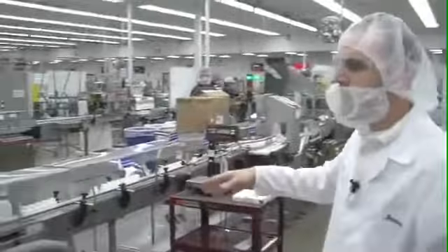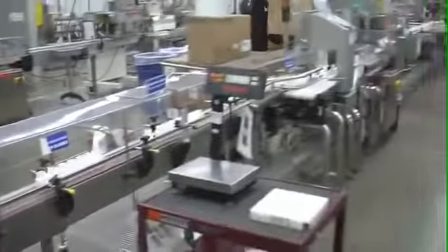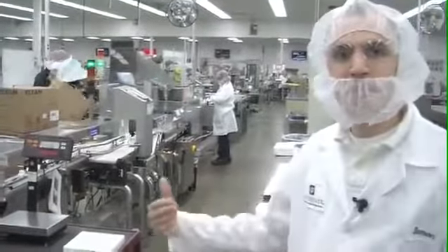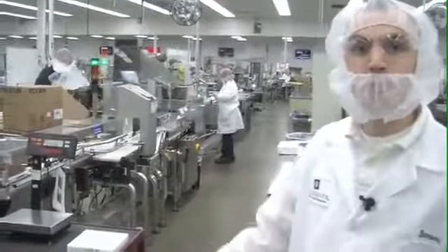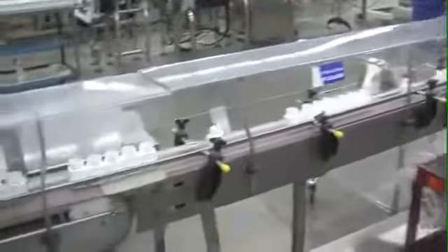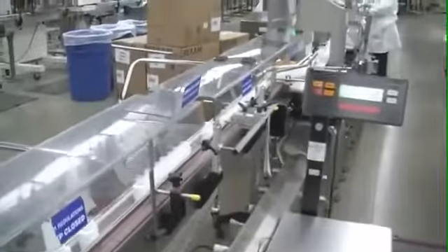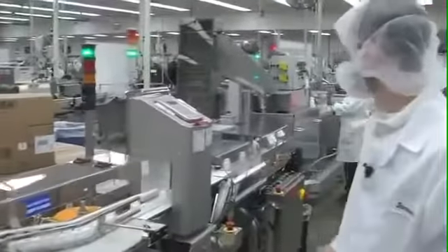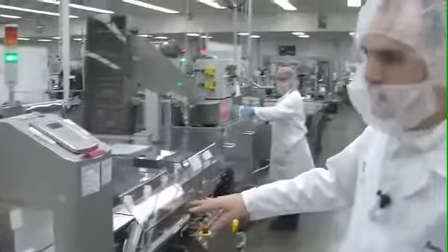After you go through that, the conveyor belt's going to go through a check weigher. This check weigher is going to see if a bottle is too light or too heavy. Too light means that they don't have enough tablets. Too heavy means that they have too many tablets. The conveyor belt will just shoot those bottles off the line so that there is a consistency with all the tablet numbers. Going further through the line, we go through the metal detector.